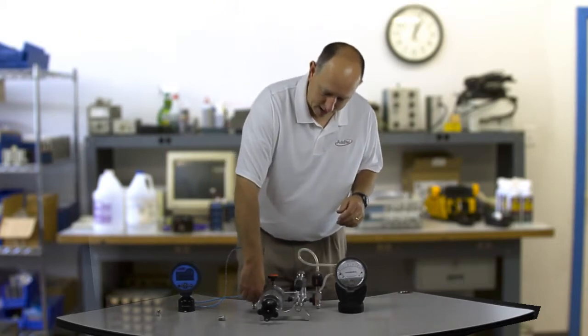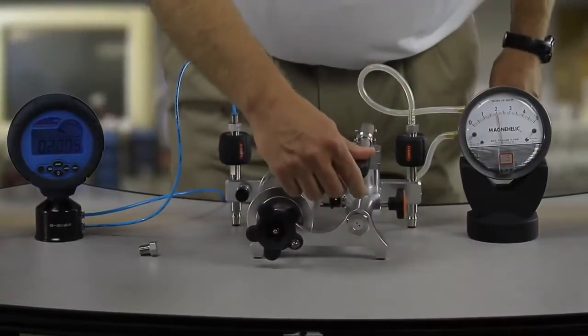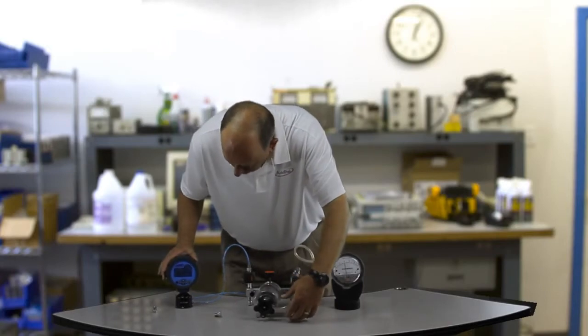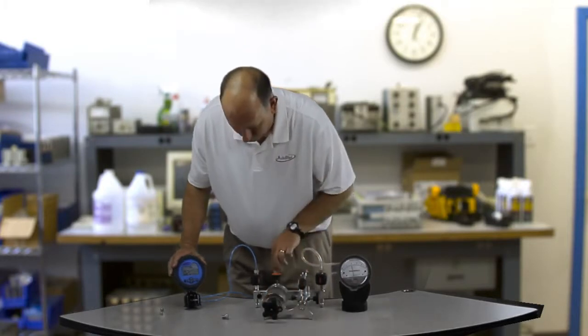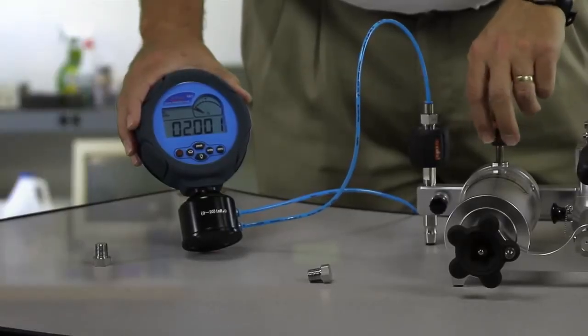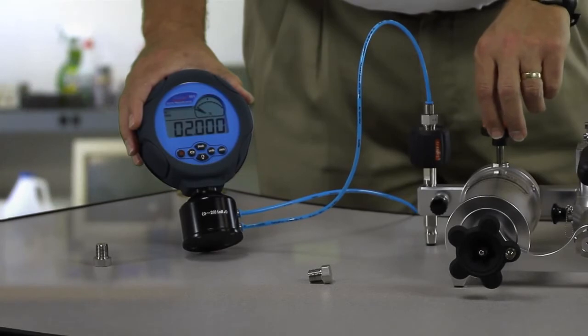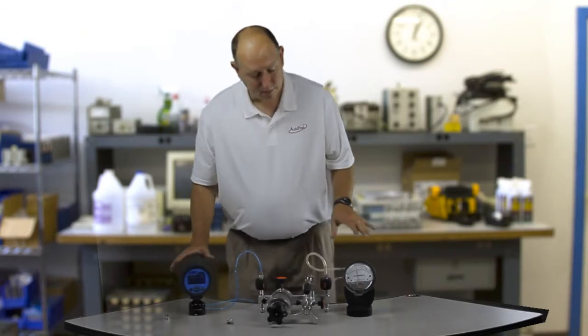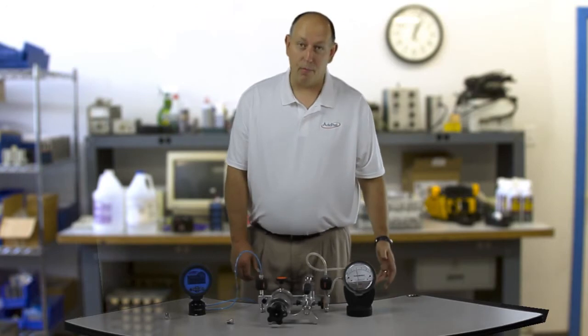I'm going to hold my vent here and use my pump to get up close to two inches of water. Looks like I went a little bit over — here's my reference, I'm at 2.076. I'm going to dial in the third digit. I've got 2.003 and I'm going to use my fine adjust here — 2.002, 2.001, 2.000. That is remarkable. This makes calibration of these Magnehelic gauges very, very easy and solves a lot of problems.